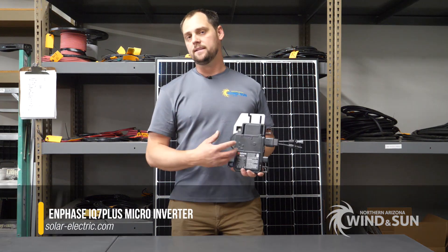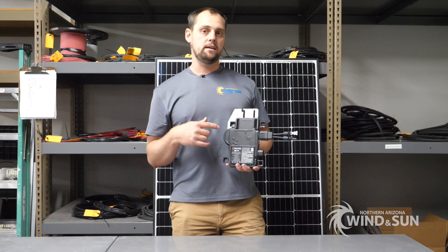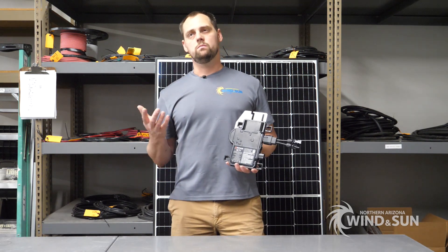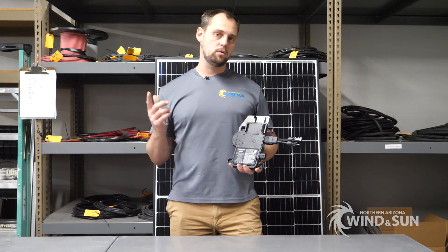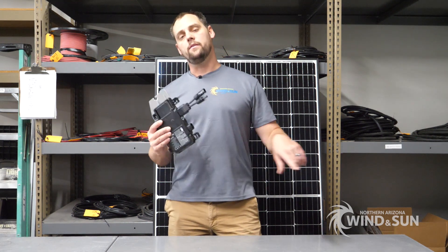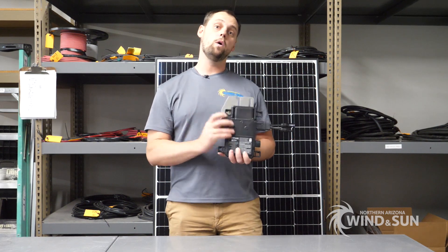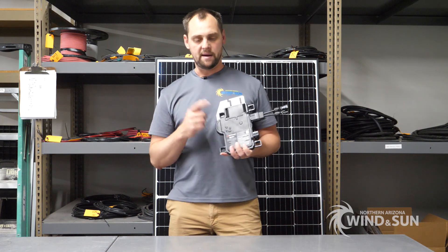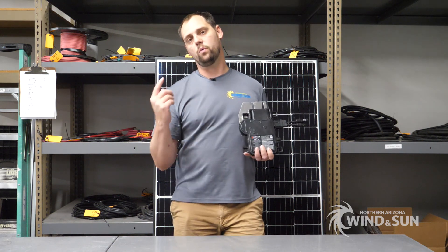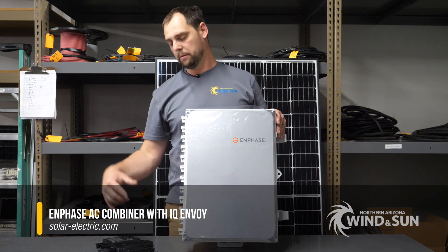Most commonly you'll use this for a grid-tie solution. This is the Enphase IQ7 Plus — it outputs around 290 watts, about 1.2 amps at 240 volts. The AC wiring on the trunk cable is 12 gauge, so you can put 13 of these on one home run, for a maximum of 13 on a 20-amp circuit.